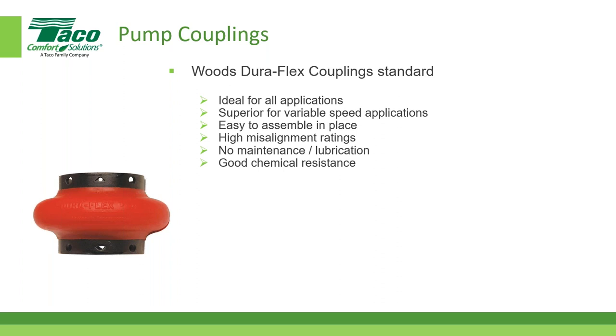If you read our instructions from an alignment standpoint, those shafts have to be within 5/1000ths vertically, horizontally, and angularly. So there's a whole process of how you need to make sure those are in alignment. Most of our reps will offer that service for final alignment. And we do recommend, especially on the bigger pumps, that the final alignment is done with a laser alignment. So again, you could talk to your manufacturer's rep for more information on that and what abilities they have.